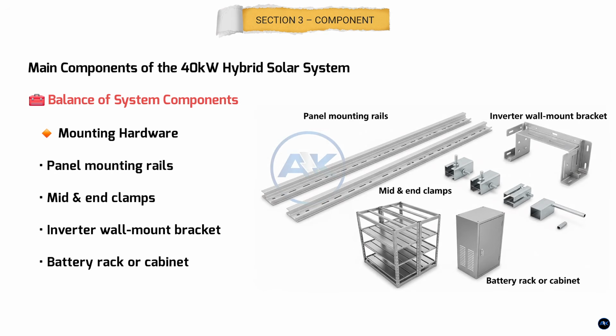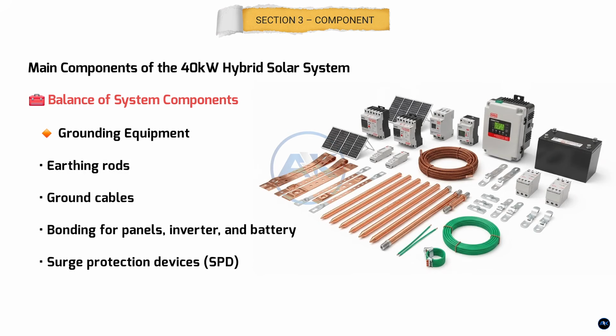Mounting hardware such as rails, clamps, inverter brackets, and battery racks ensures that all components are securely installed and properly supported. Finally, grounding and earthing equipment is installed to protect the system from electrical faults and lightning. All panels, inverter, battery systems, and metal structures are bonded to a common grounding system.